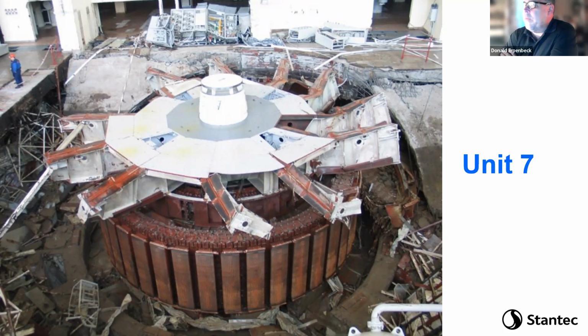We might close it a little bit faster, but these are massive amounts of force, and you've got to be careful how fast you stop it. So 2 minutes is fairly fast for this big of a gate. We don't know their justification for 2, but it does need to link with the turbine design, and the turbine has to be able to take that overspeed for a certain amount of time, and you have to be within that time.